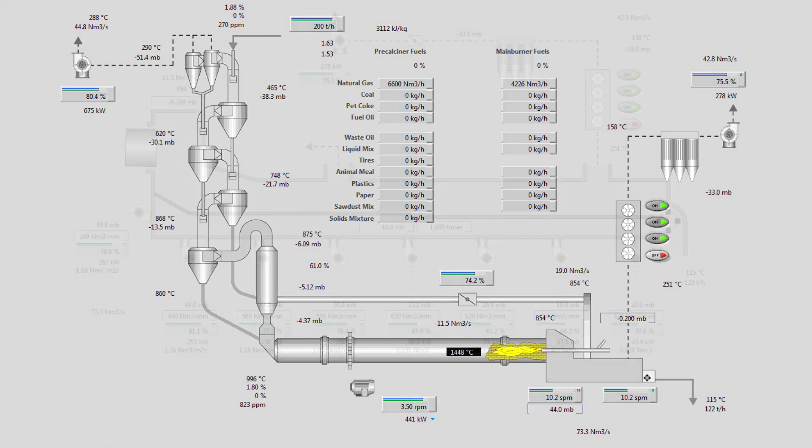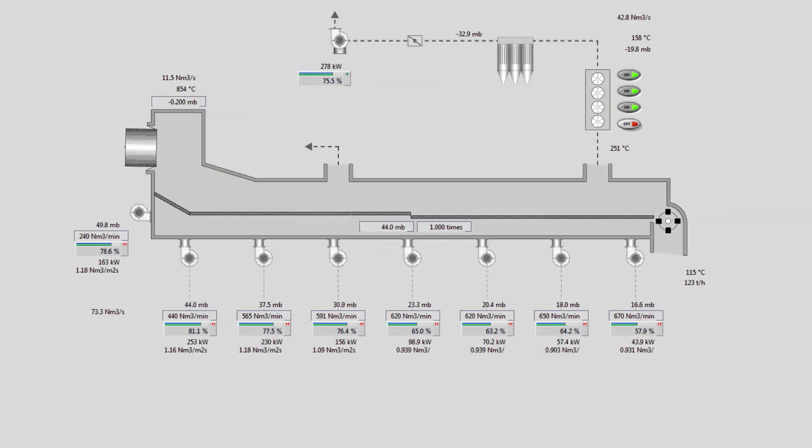We can see the cooler. And going into more details. Notice the secondary temperature at 854 Celsius, the clinker temperature at 115 Celsius, the under-grate pressure at 44 millibars. Notice that we take this reading from fan 2. It is usually done this way since pressure at fan 1 is normally unstable.